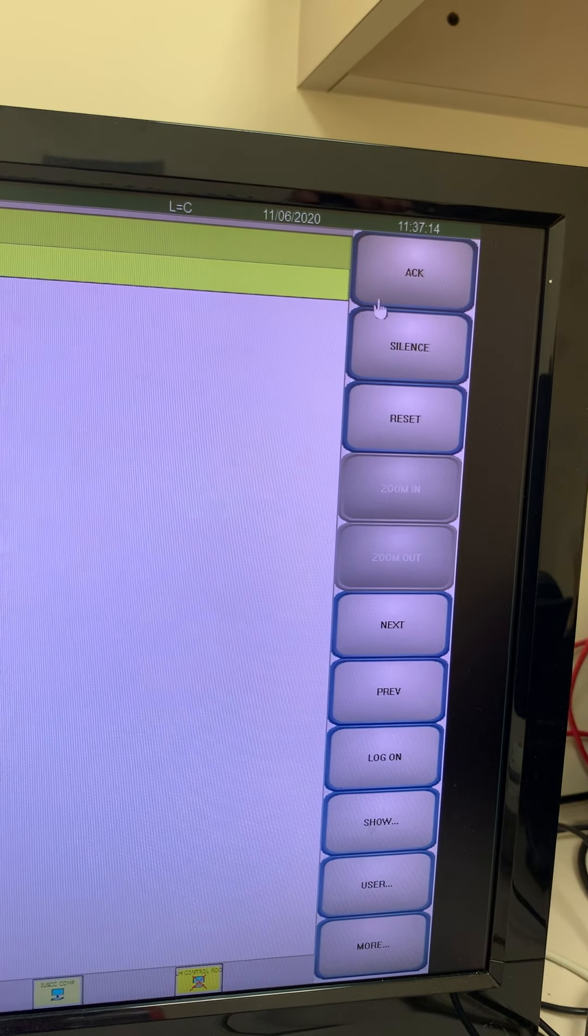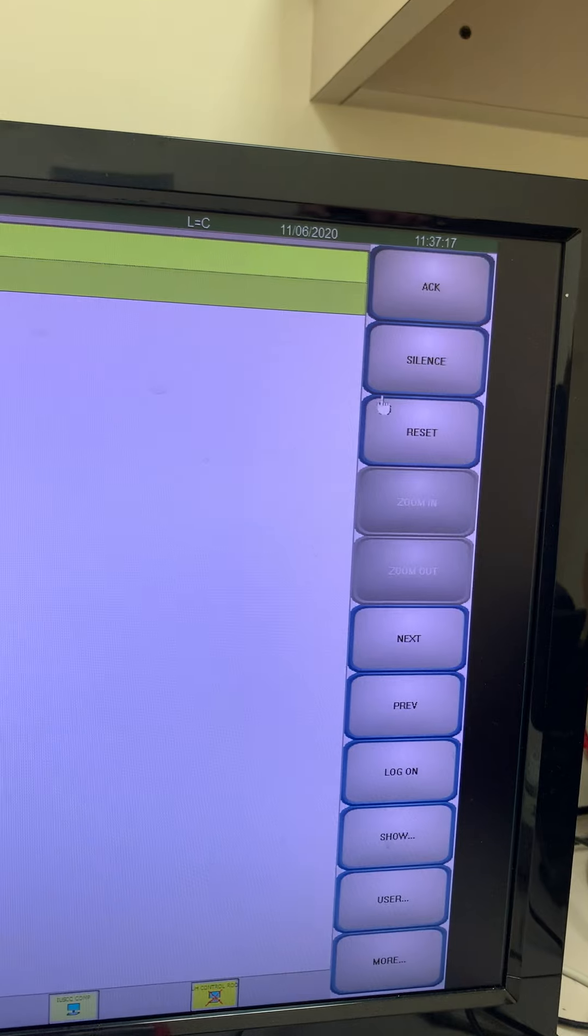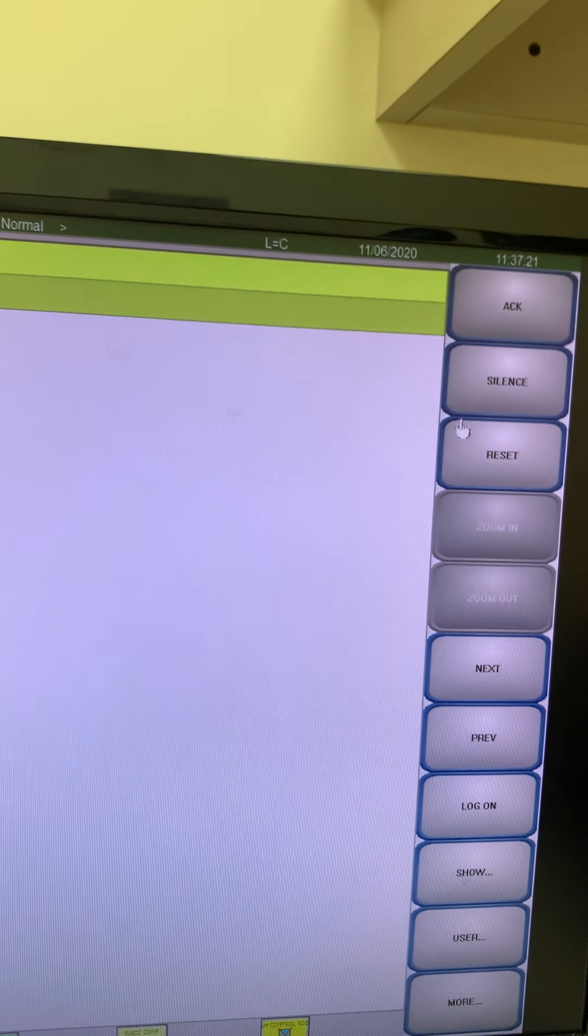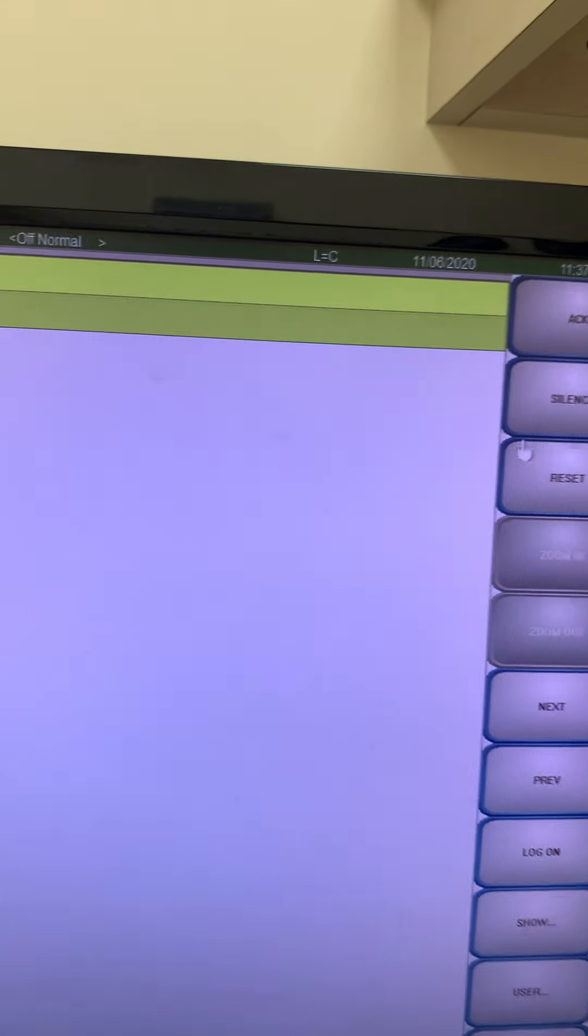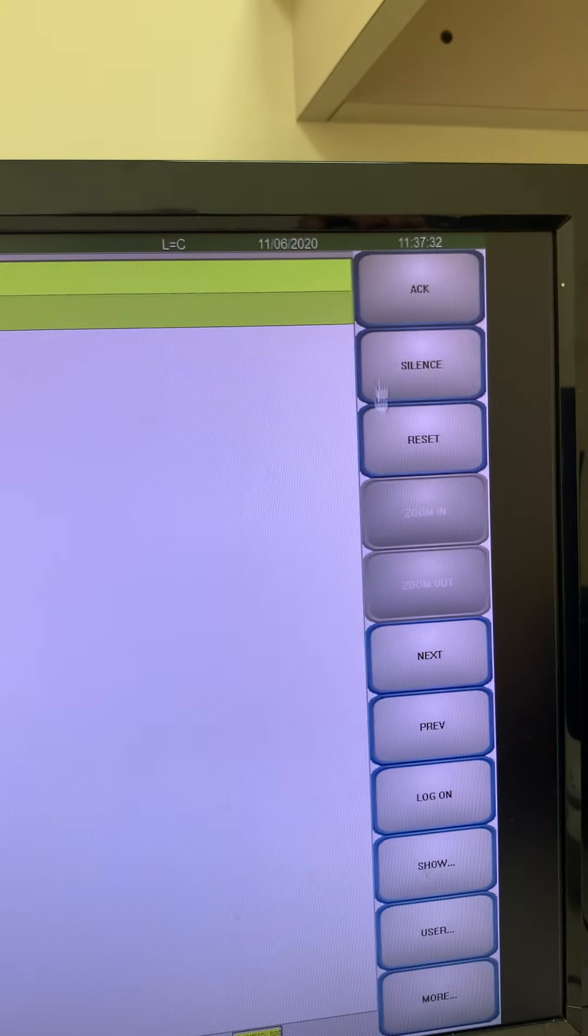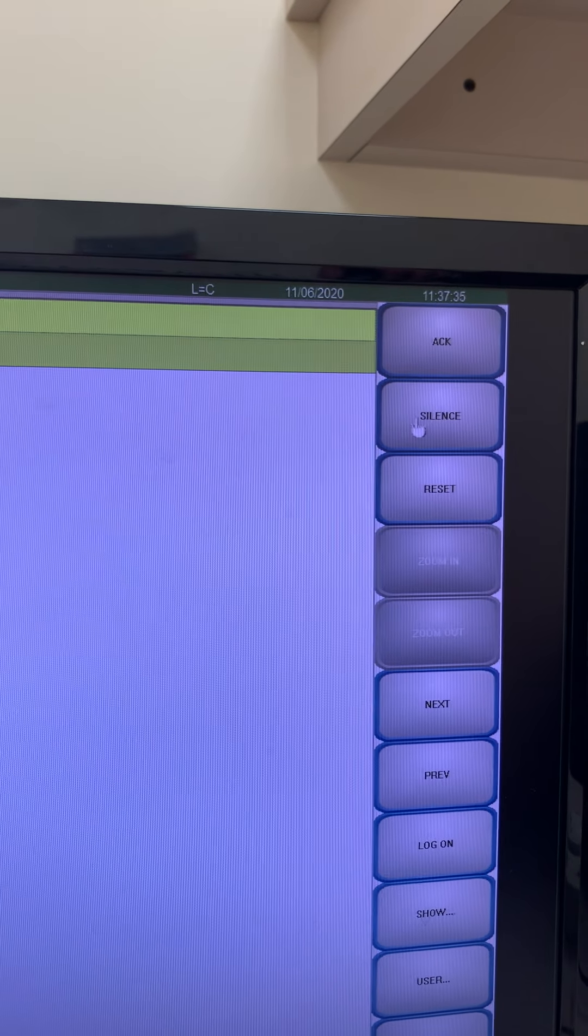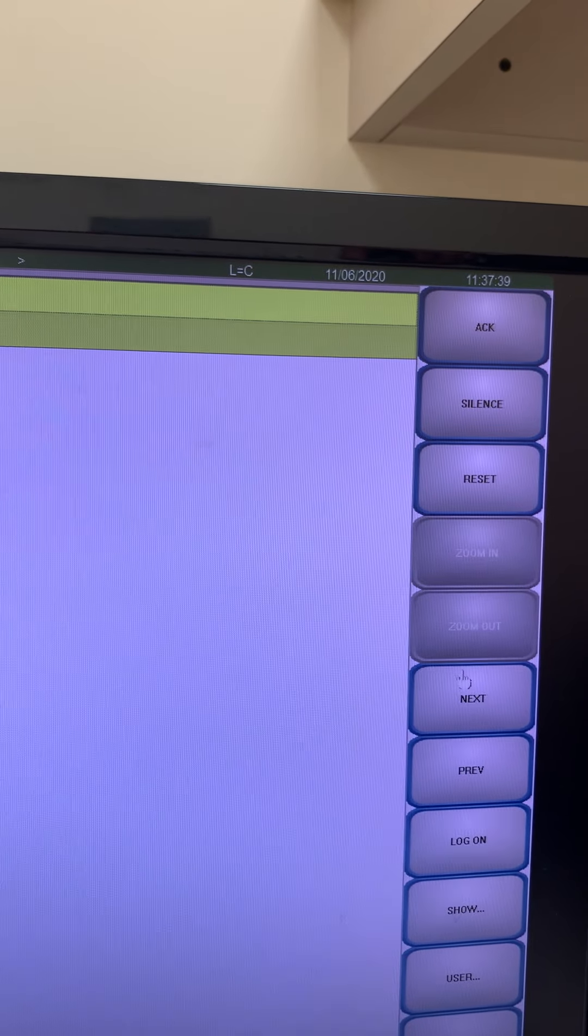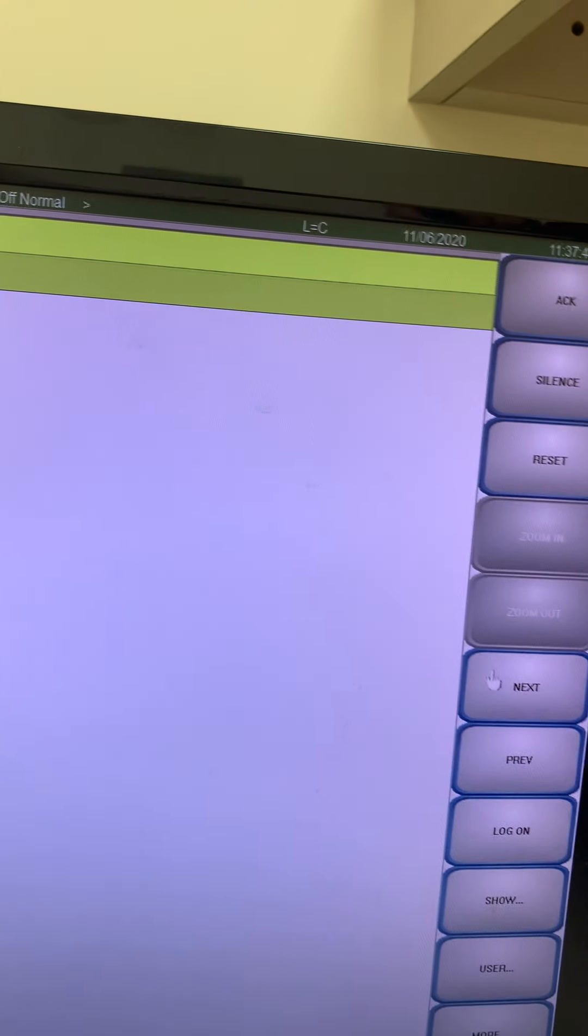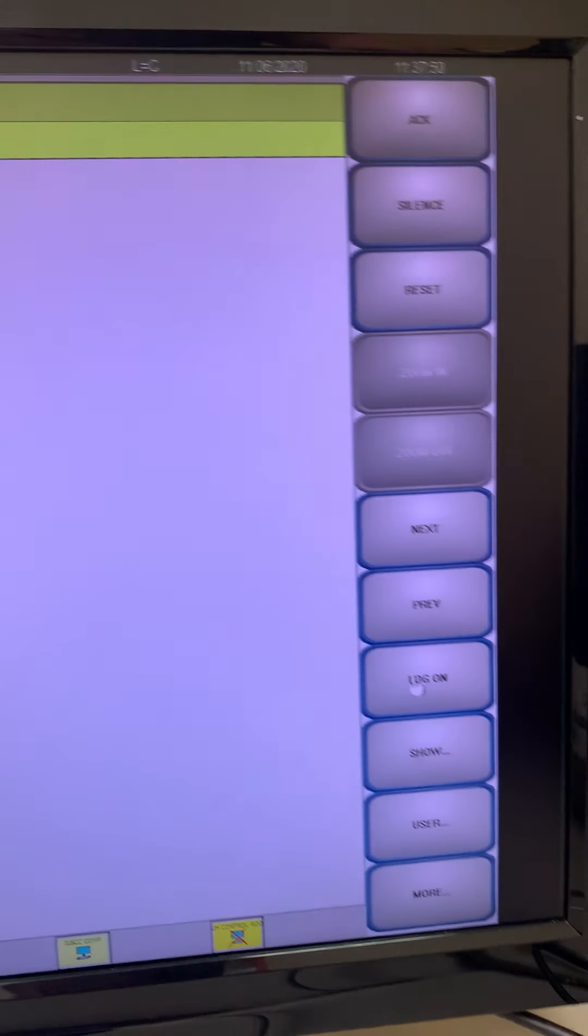I'll show you a couple other features real quick. You have all these buttons over here on the right side of the screen: acknowledge, silence, and reset, just like a regular fire alarm panel. When you have an alarm come in on any one of these nodes connected to the system, it shows up right here on the screen, same with supervisory, troubles. We can acknowledge it, hit the silence button, reset. This is like a scroll feature if the list was that big, or it just highlights the next device on the list when I click it.